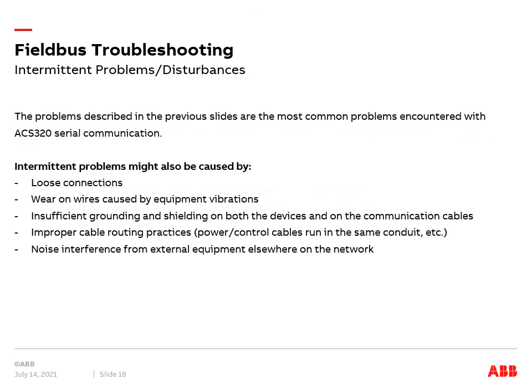Let's take a moment to talk about intermittent problems and disturbances. The problems described in the previous slides are the most common problems encountered with ACS-320 serial communication. Intermittent problems might also be caused by loose connections, wear on wires caused by equipment vibration, insufficient grounding and shielding on both the devices and on the communication cables, improper cable routing practices — for instance, power or control cables run in the same conduit — and lastly, noise interference from external equipment elsewhere on the network.